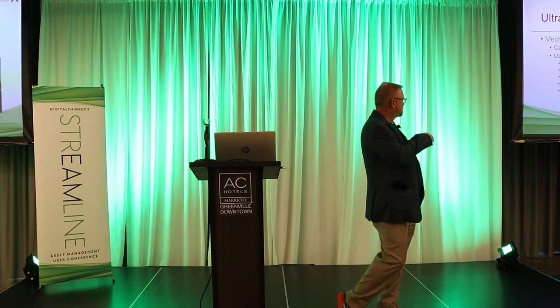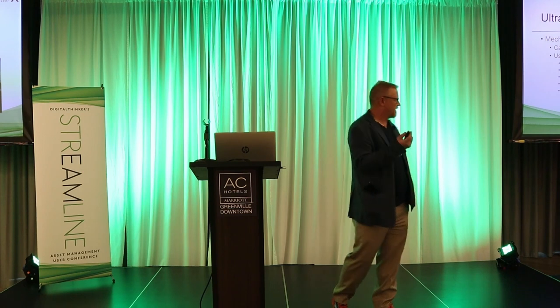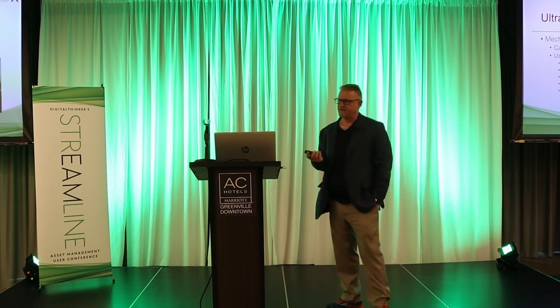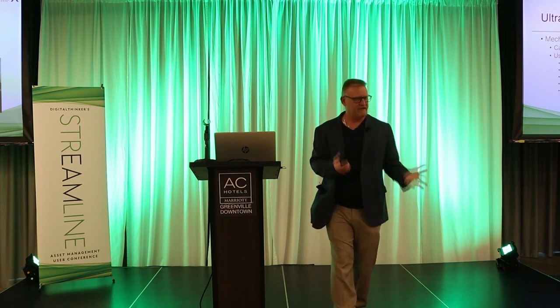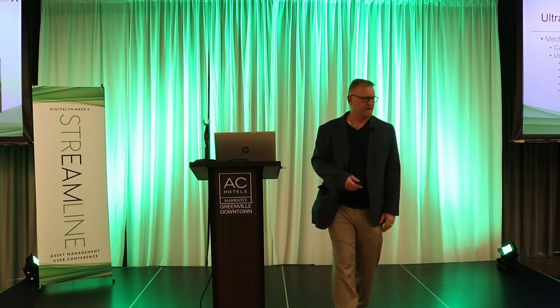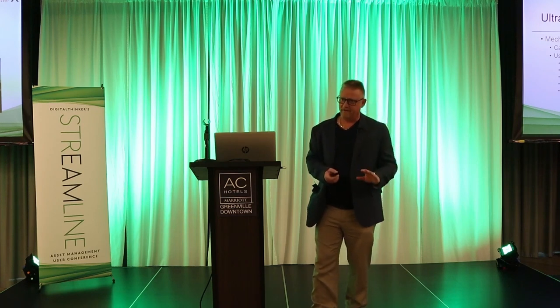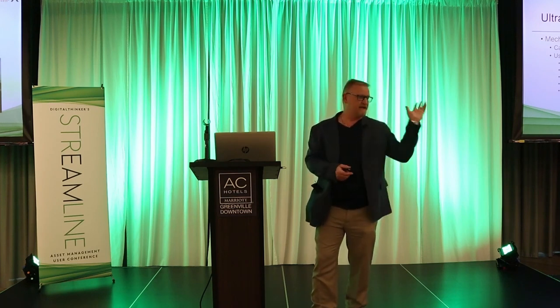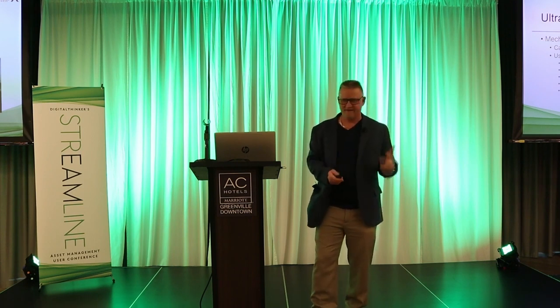From a mechanical inspection standpoint, bearing issues, pump cavitation, steam traps, underground leaks, you can actually get what's called a grease caddy, bolt onto it, and you can do lubrication based on sound. So you listen to the bearing, apply a little bit of grease, hear it get quieter. And if the noise comes back, you don't just keep pumping more grease in. That means the bearing's no good.